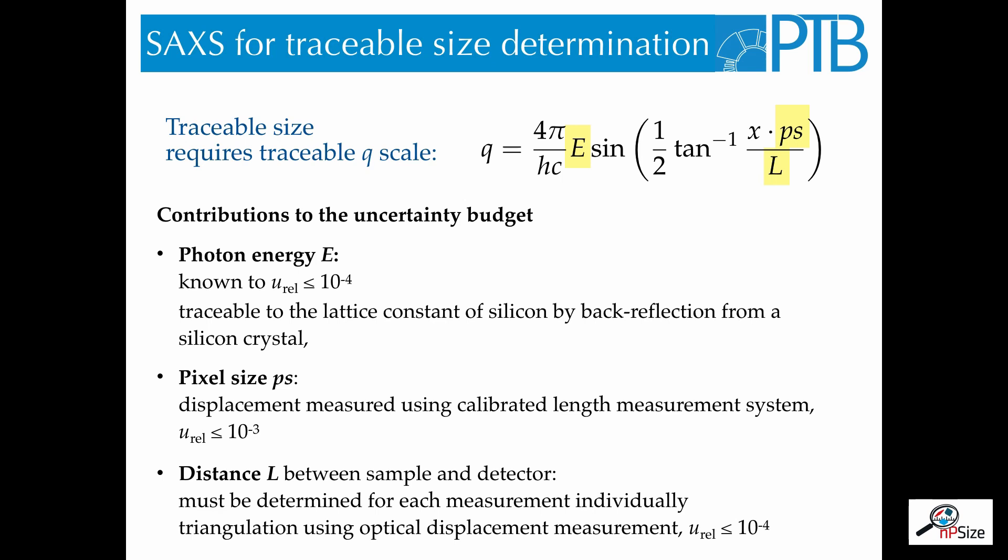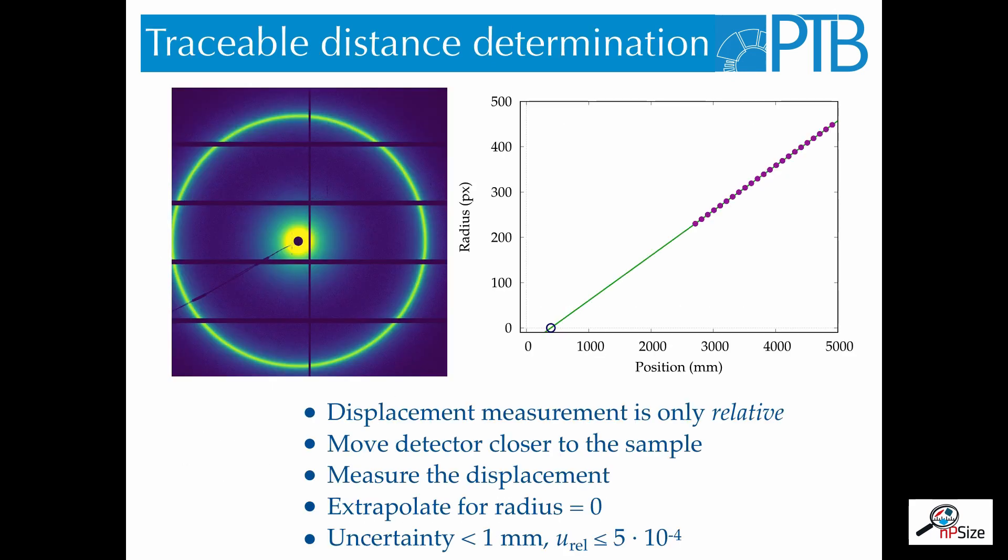Finally, the distance between sample and detector must be determined for each measurement individually. For this, we have optical encoders, which measure very accurately the position of the detector. But this optical measurement system gives us only a relative displacement of the detector. In order to get an absolute position, we use a standard sample.